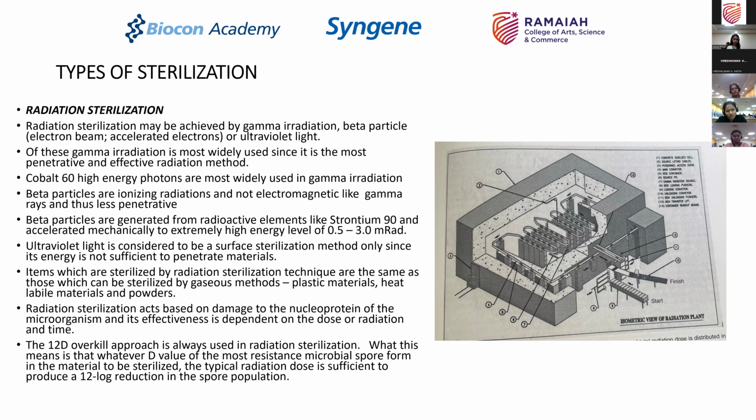A lot of times when you assemble a device, because now people use self-administration techniques, or even doctors use devices with a dose to administer the medicine to a patient, those devices need to be sterilized, sometimes post manufacturing, and there again gamma irradiation is a technique which is used. Any material which is heat labile, radiation is a good technique for it.